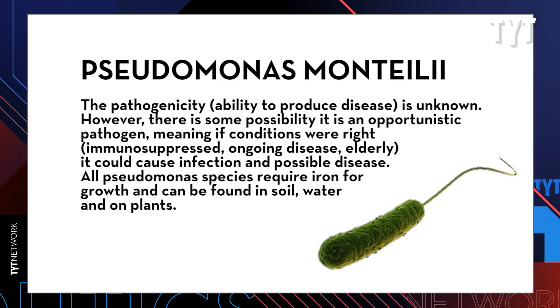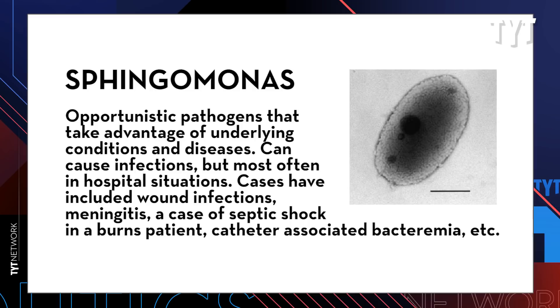People will get to lead, but it's a lot more than lead in the water when you get these compromised symptoms. Pseudomonas — we're finding it in Flint and East Chicago — that lives off iron. We have control cities where we didn't find it: Traverse City, Michigan; Riverview, Florida; Brooklyn, New York. And there's another one called sphingomonas, which is copper-related. What we just discovered with sponge testing is that we can have a marker with this bacteria that may suggest you have compromised pipes.